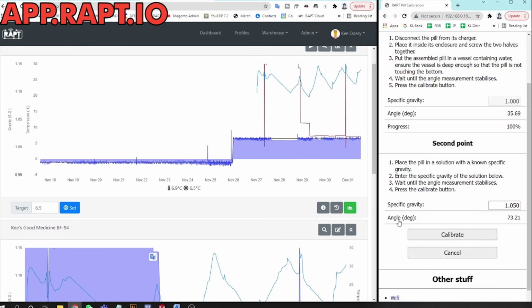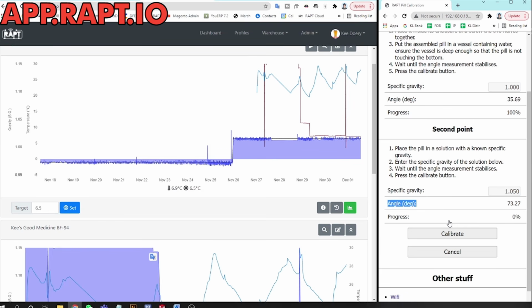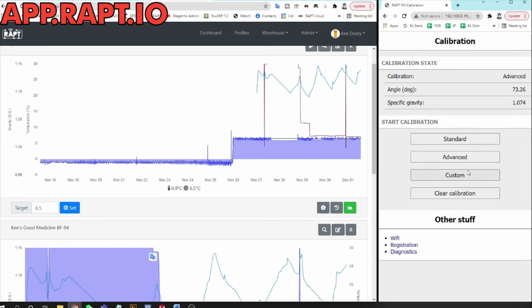And once again, now the angle is sitting at 73.21, and it's kind of stabilizing. Look, it's bobbing up ever so slightly in the liquid there. And then I hit calibrate. So that's a 2-point calibration. Now, when you're doing 2-point calibration, we definitely recommend using water as one point. And then for the second point, we'd recommend using a fairly normal gravity that you would use for whatever it is you're fermenting.